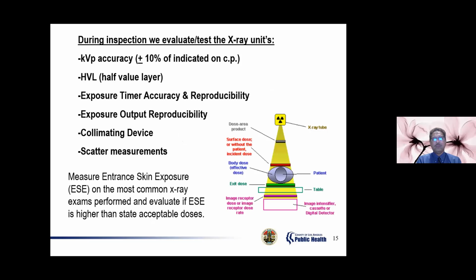The type of things that we check is the kVp accuracy. You guys are familiar with kilovoltage peak accuracy, plus or minus 10% of indicated on the control panel. If you put 80 kVp in there, and we carry a lot of radiation meters, and we measure 90 kVp, that means your patient is getting too much dose, right? Because you put 80 kVp on your dial, but it's actually giving you a higher value. So those are the type of things we look at. HVL is not an issue right now. Most of the machines out there pass, but we still check half-value layer anyway.